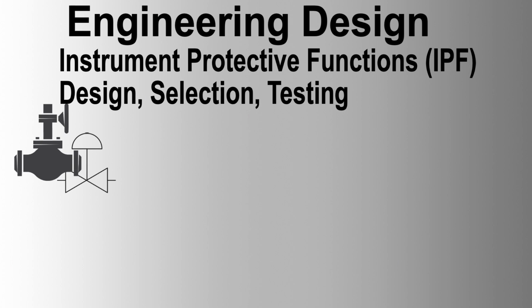Engineering interface. The engineering interface should be such that group modules can easily be displayed. It should be possible to view the status of input and output signals and the actual values of inputs in engineering units. It should be possible to view the status of intermediate points in the logic. Access should be password protected or under key lock.